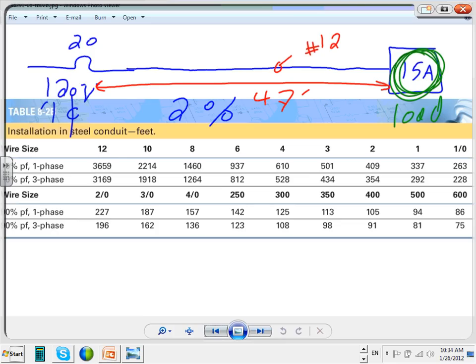Anybody can tell me why I can't apply this to these lights? For one simple reason. Are these lights all located 47 feet away from the load? No. There is one fixture, if I come with a branch circuit here, that is probably 10 feet. The other fixture way at the end is, say, 25, 30 feet. So how am I going to do that when the loads are scattered all over? This only applies if a chunk of load is thrown in one corner.